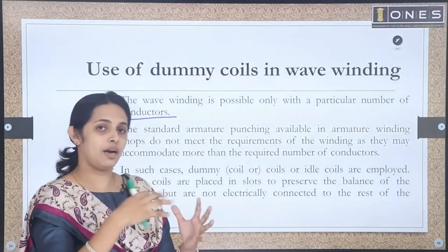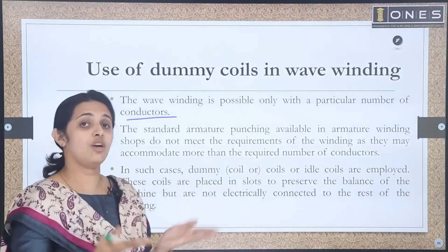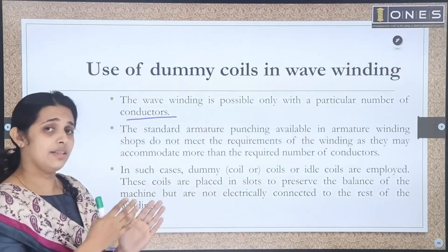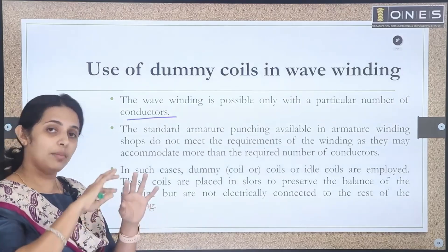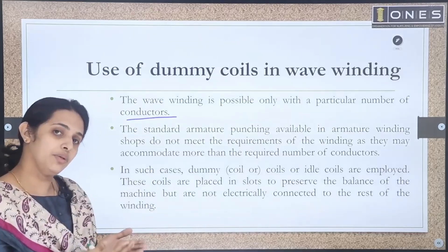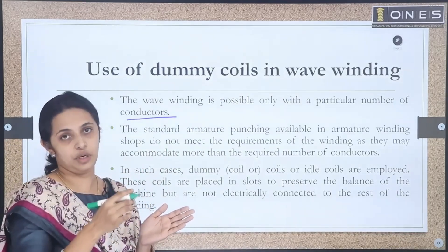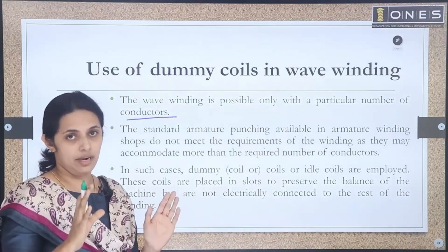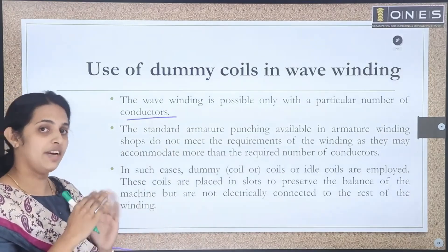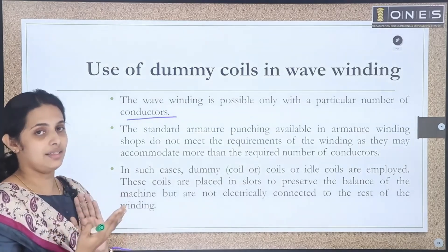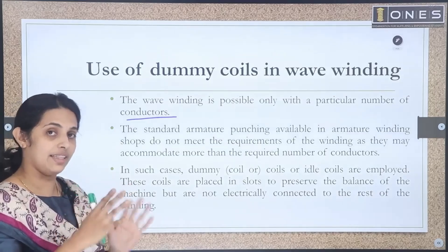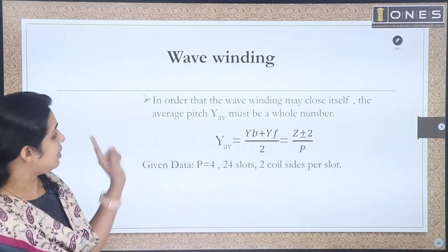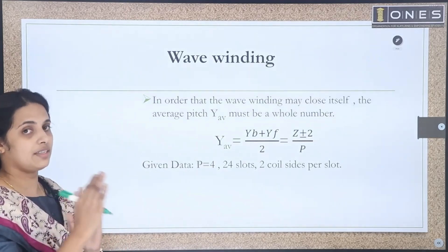If we use standard armature punchings, there will be a fixed number of slots, and all slots must be used. If a particular number of conductors cannot form a closed wave winding, we place dummy coils in the vacant slots to maintain mechanical balance of the armature. The dummy coils are electrically isolated but physically placed to balance the rotor.